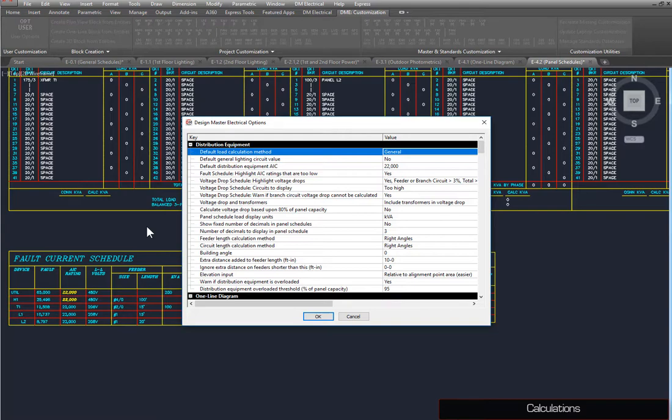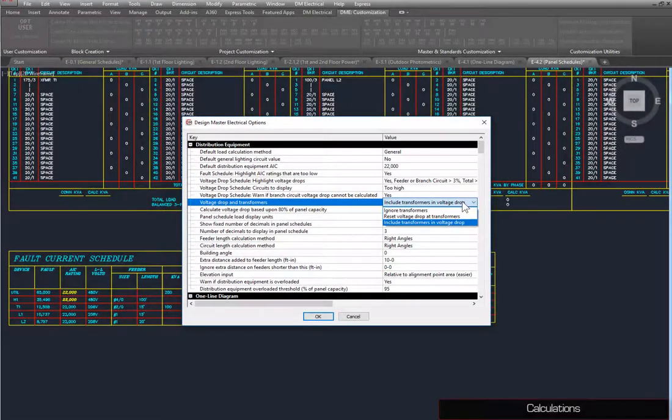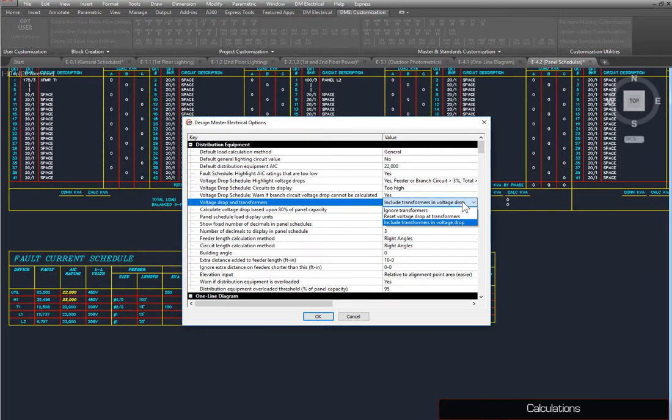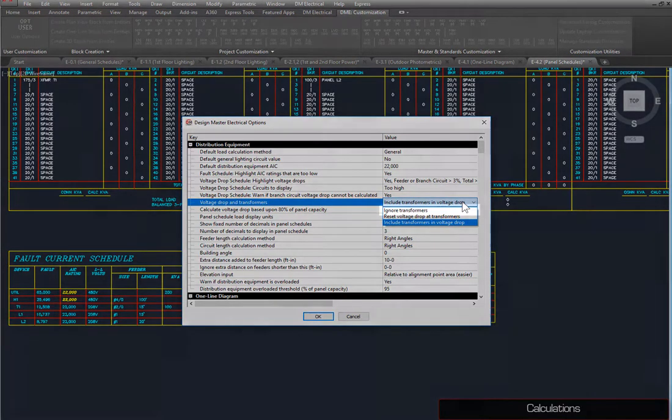This dialog box allows you to set options for various aspects of the project, such as Default Calculation Methods, Graphics, Values, and Callouts. In the Distribution Equipment section, there is an option for Voltage Drop in Transformers. Here, you have three options. Transformers are ignored for Voltage Drop Calculations. Voltage Drop is reset to zero at transformers, or Voltage Drop is calculated as normal.